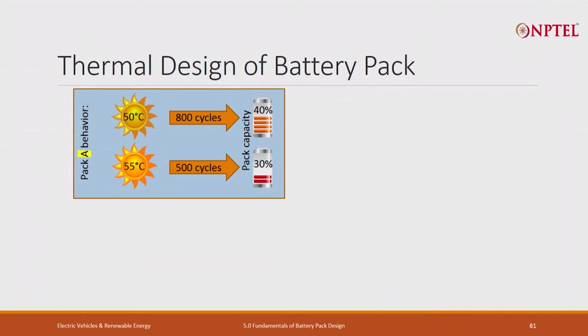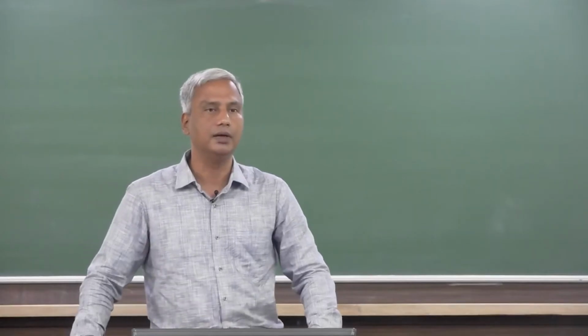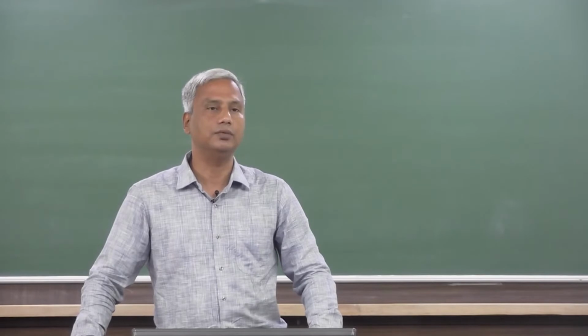As soon as you increase the working temperature of the pack, now the pack is being utilized at 55 degree centigrade, the number of cycles has come down to 500 cycles. Also my pack capacity has come down to 30%. Here in the first case my pack capacity came down to 40%. Initially we had 100%, then it came down to 40%.